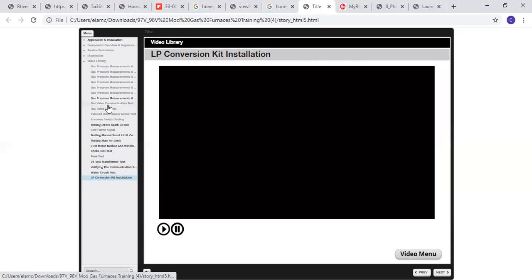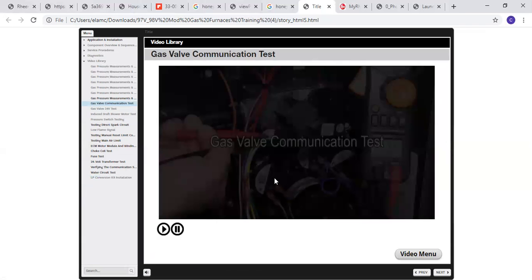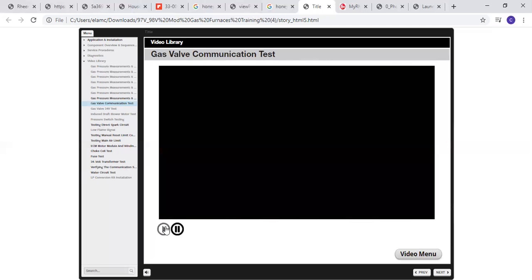Okay, we'll go on to the gas valve communication test. As we discussed in the first section, it's a 24-volt modulating gas valve, but it also has two 24-volt terminals as well as a ground, and then two communication wires. The communication wires, that's what controls the modulation point. Your 24 volt actually engages the valve. So there's a pretty simple way to test this, and this video will show that for us.